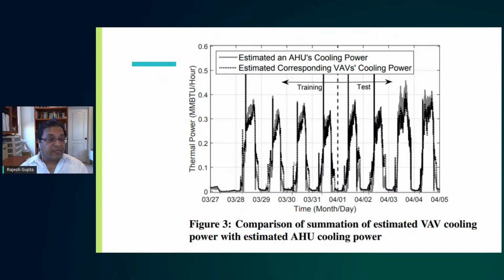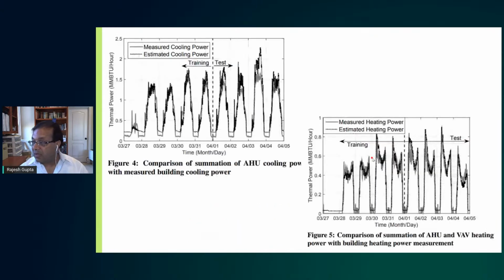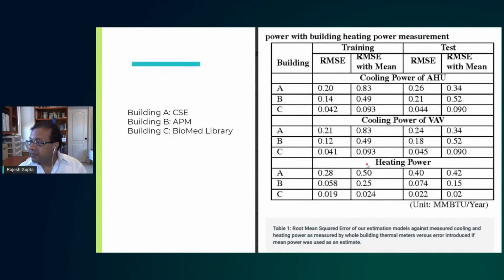So we implemented that. We actually measured the actual cooling power and heating power used by the building and compared it to the power estimated from the airflow. And when we do that, this is the summary of that. We ask, what is the root mean square error for 3 different buildings? Remember, this is where the discovery across buildings comes in. And how do I compare it? If I compare it to, let's say, where I just use the mean value as an estimate, you can see there's a significant improvement in the error simply because of actually taking the airflow and measuring that.